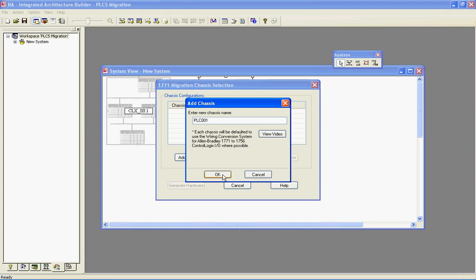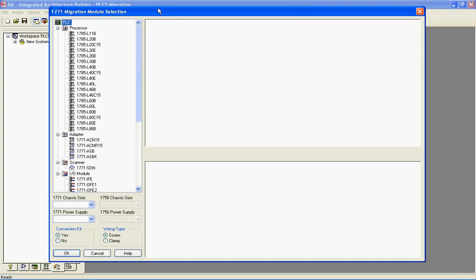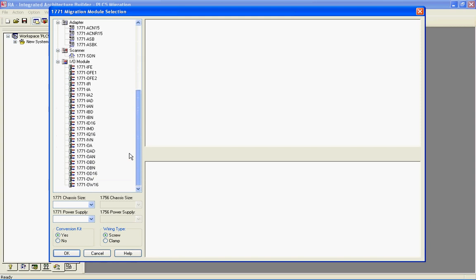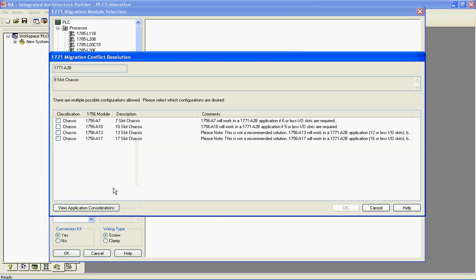From here I can click Add Chassis. It allows me to name that chassis if I want to — I'm just going to leave it as default. Click OK, and it opens up a window that allows me to lay out my current PLC-5 system. I'm going to say I've got a current A2B PLC-5 chassis, and I want to convert that to a ControlLogix A7 7-slot chassis.